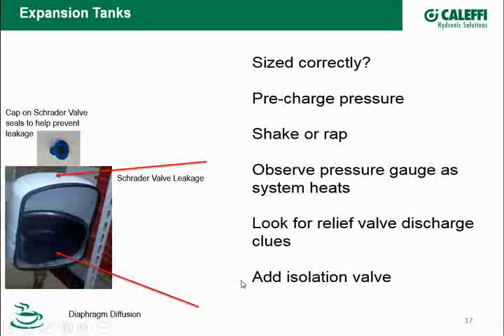There are a lot of nice isolation valves. If you're going to put an isolation valve on here, it's a good idea to get one that's called a lock shield, that you can lock it in the on position so that a homeowner or somebody might come and say, oh, that valve should be in the off position, and inadvertently turn the valve off, and then you've taken this out of the system, and now you're going to have a discharge on your relief valve when the boiler heats up. So most of the valves that are out there now that are made for isolating expansion tanks have a side port that you can drain the pressure off.